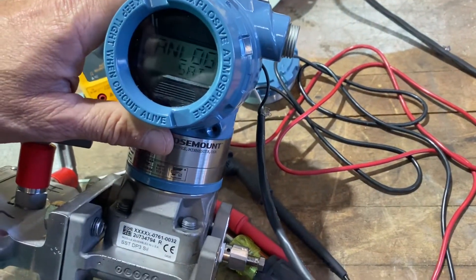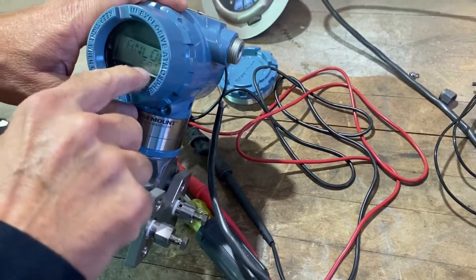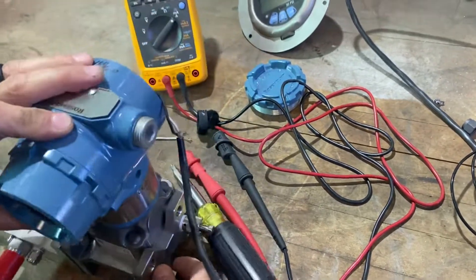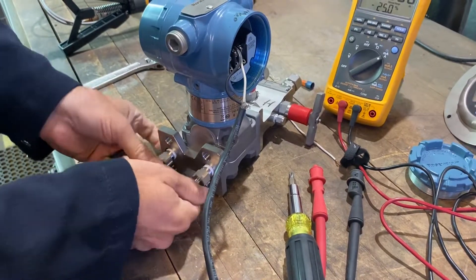And that would be on the face of the meter. You can see right now it's reading 0.1 inches, or 0.8 inches. So, it's reading negative, so it's saying analog saturated. You want to make sure it's zero, and that's how you check the zero.